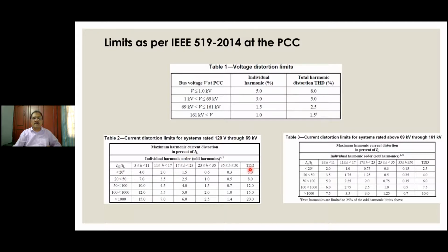The limits are for TDD, total demand distortion. THD is based on fundamental current. TDD is based on the average load current for the last 12 months. So that is the only difference. The same numerator, the denominator alone will change. And this is decided by the ratio of short circuit current to the load current for 12 months. Typically, I find in the Tamil Nadu industries, the ratio of 50 to 100 is applicable. Most of the industries will be required to meet 12% TDD or below. Some will come in 8, some might come in 15.